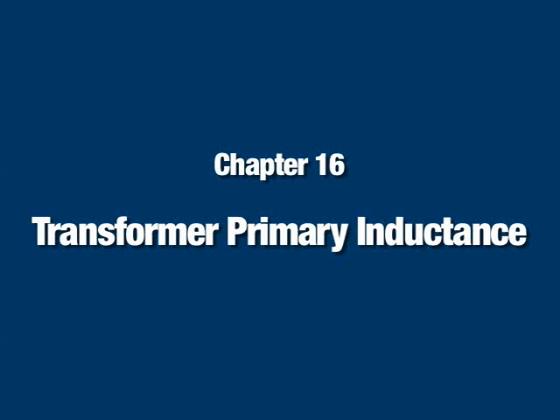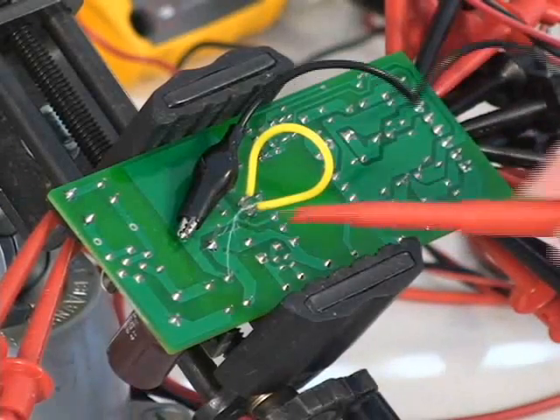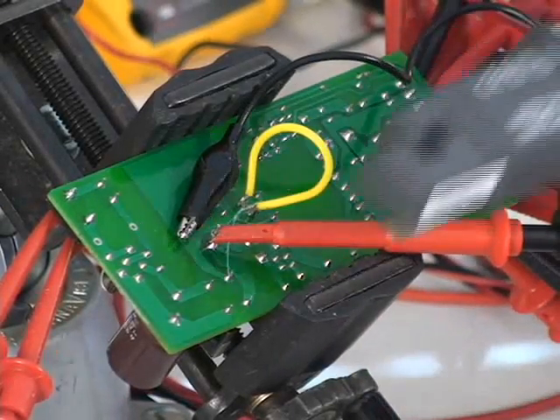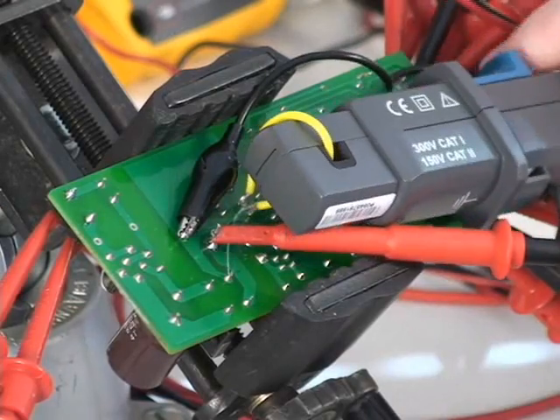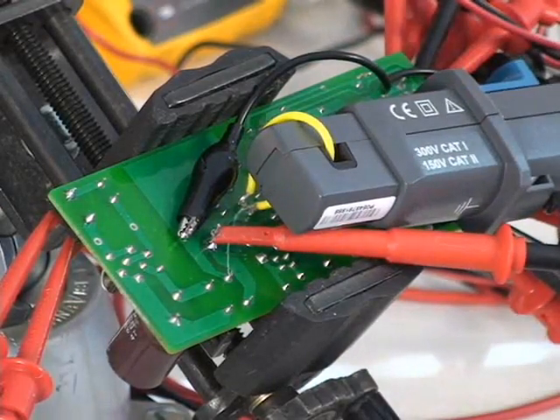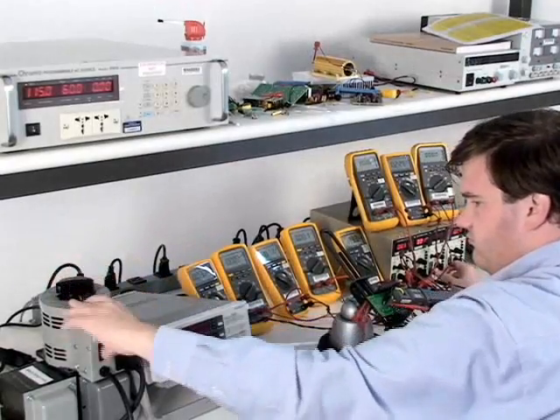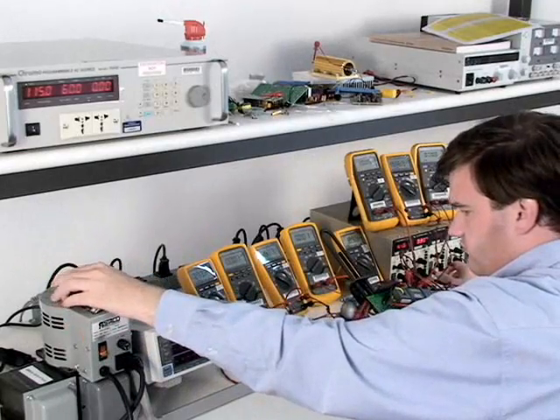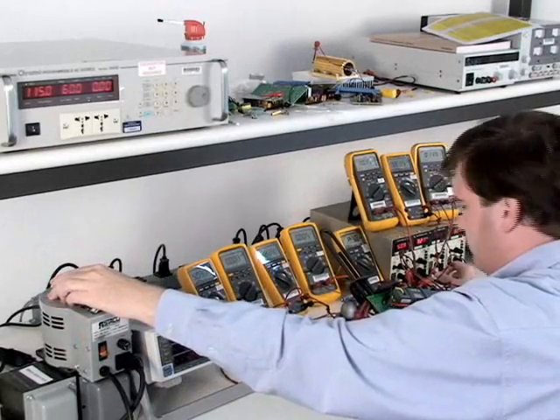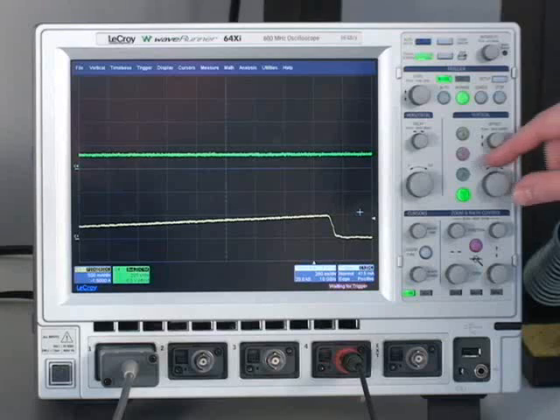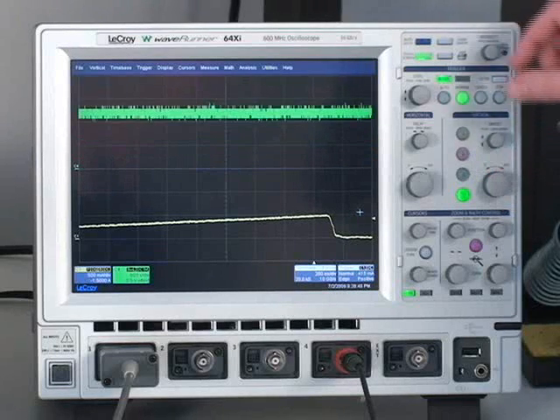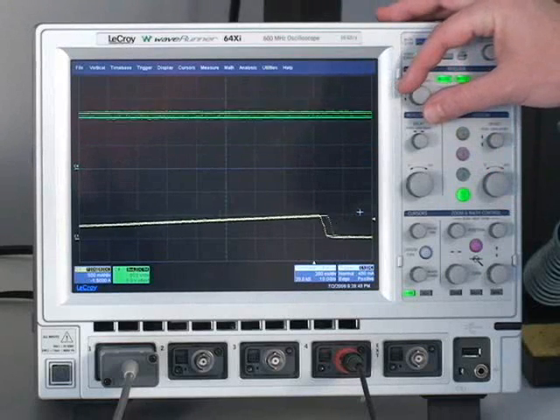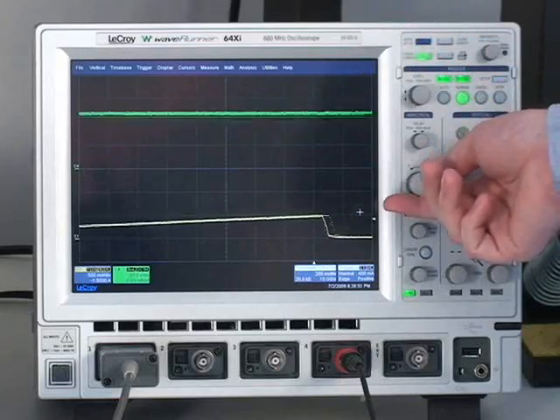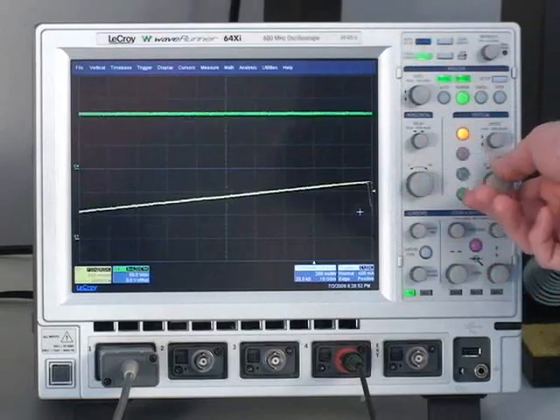Chapter 16. Transformer Primary Inductance. Now turn off the AC input and connect the high voltage oscilloscope probe across the terminals of the input bulk capacitor. Then apply the minimum AC input to your supply and increase the output loading to full load. Configure the scope to view both the DC bus voltage, seen by the high voltage probe connected across the bulk capacitor, and the drain switching current.